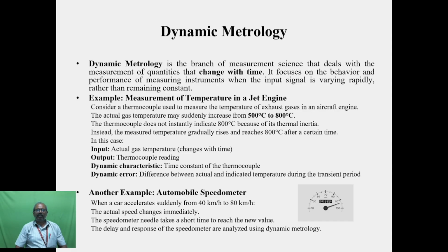In this example, the input is the actual gas temperature, which changes with time, and the output is the thermocouple reading. The dynamic characteristic here is the time constant of the thermocouple. The dynamic error is the difference between actual and indicated temperature during the transient period.